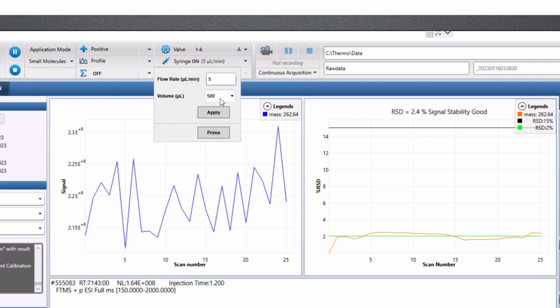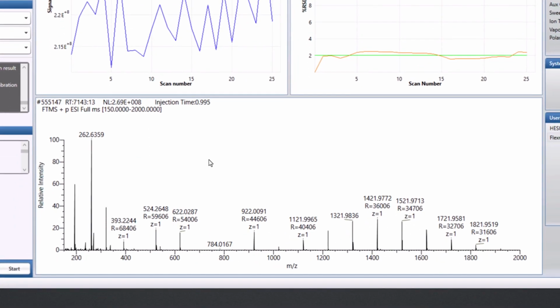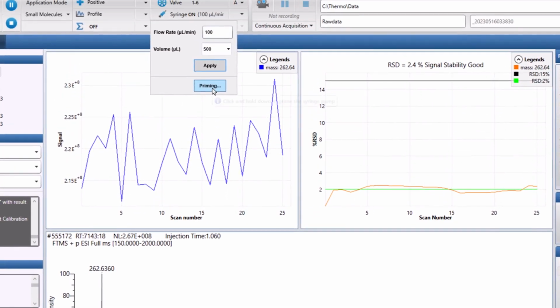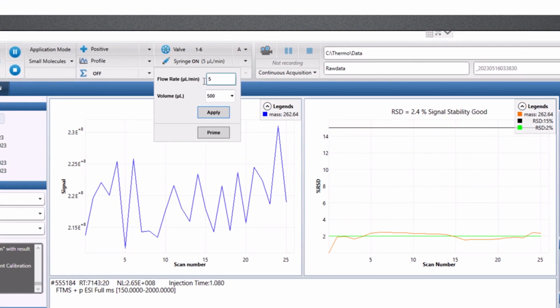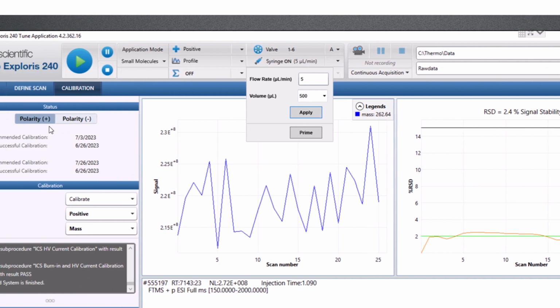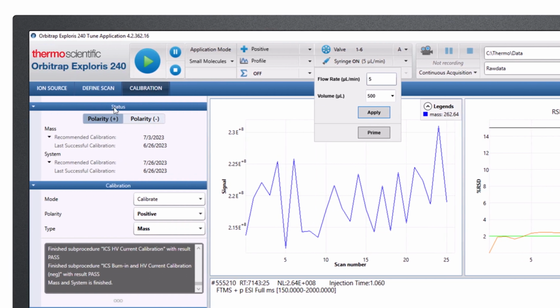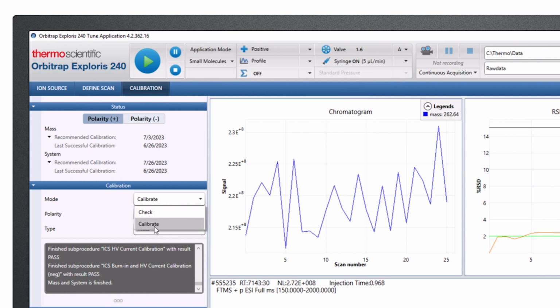Now, one nice feature here is I can prime it pretty quickly, push some solution through so I can get my flex mix over to the mass spec. So you can see the nice display of ions that are coming through. And I'm done priming here, so I'm going to go back to 5 microliters per minute. So on the calibration tab to the left, I have positive polarity selected. On mode, I have calibrate. Then I select the positive polarity, and I have a few options.